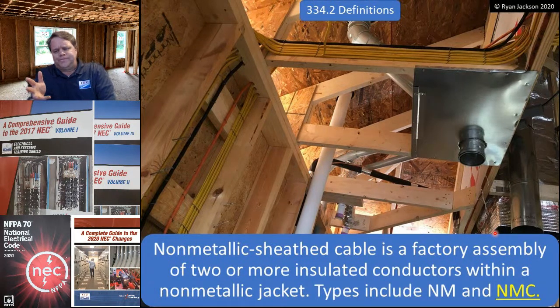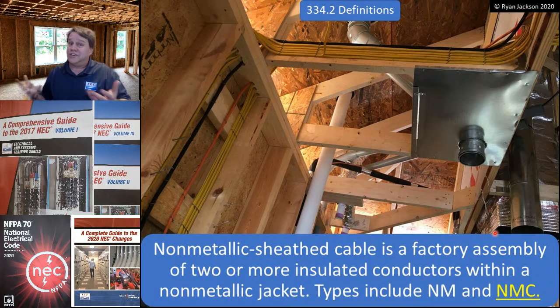Here's the thing about NMC. Nobody really makes NMC unless it's also dual-listed as UF. Because if you're going to go through the trouble of making a fungal-resistant, corrosion-resistant cable with a nonmetallic jacket, if you look at Article 334 for NM and you look at 340 for UF, there's just a lot more you can do with UF cable. So if I'm a manufacturer, why would I manufacture NMC with its limited uses instead of making UF cable that has a lot more permitted uses? So we'll mention that NMC is a thing, but to be honest with you, if I've ever seen it in the field, I didn't realize it. Again, because it's going to be dual listed as UF.